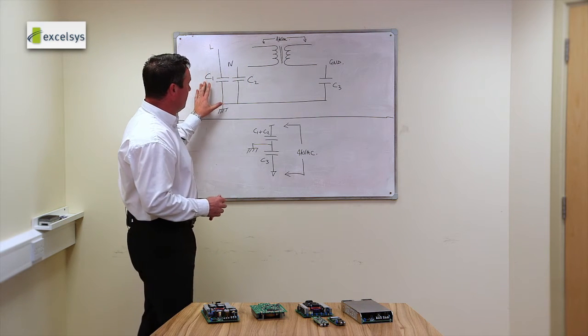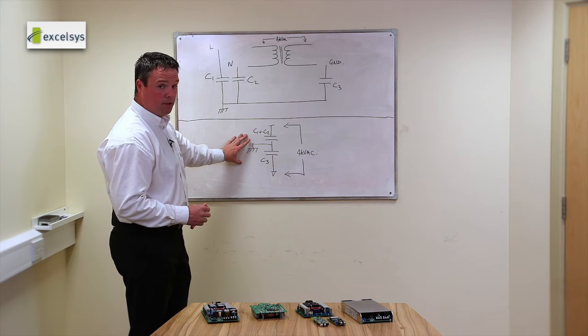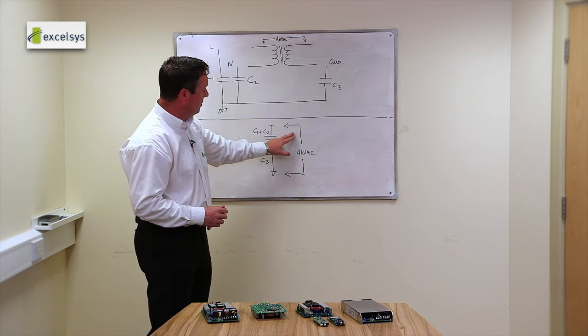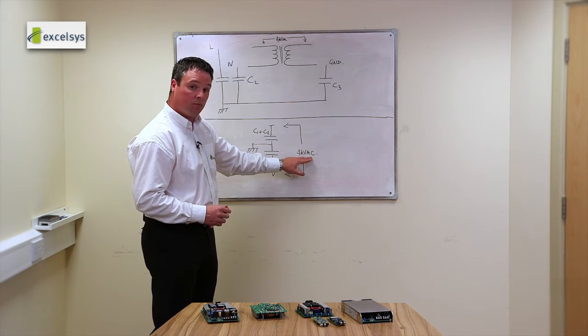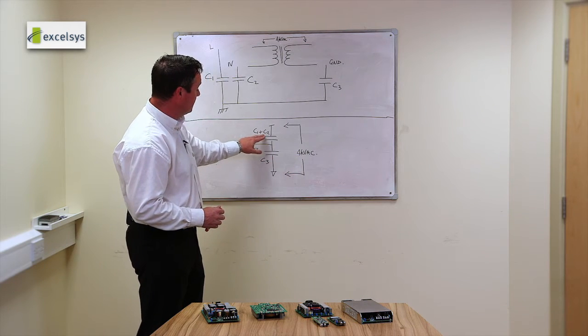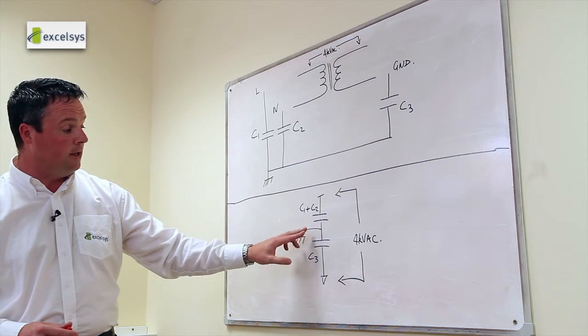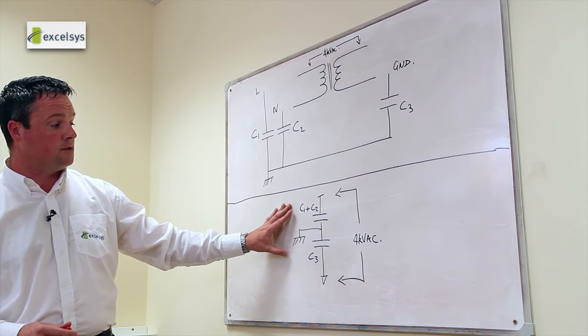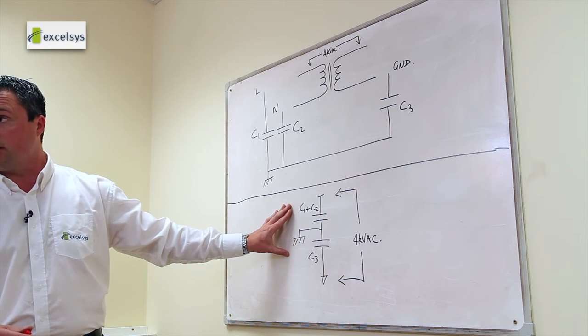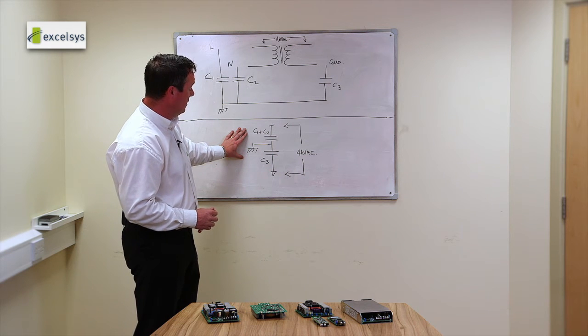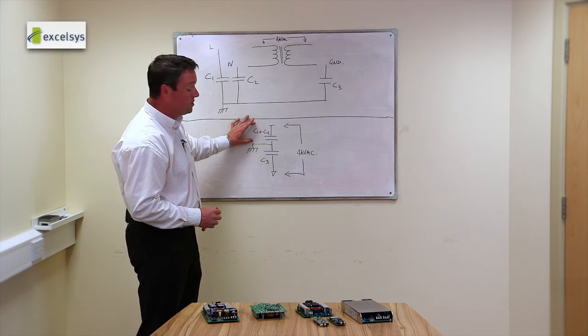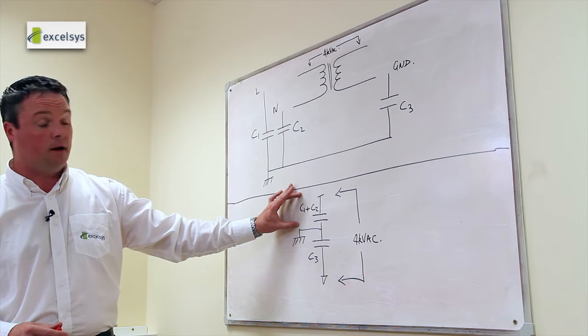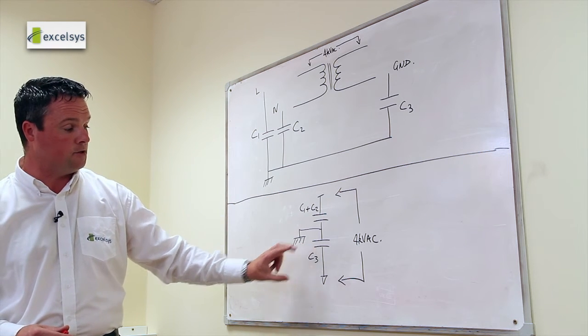So if we take this equivalent circuit and redraw it down here, you'll see that we apply 4kV AC across C1 and C2 in parallel and then in series with C3. Now very quickly you can start to see why damage may occur here. And the reasons for are the voltage divider effect on a combination of C1 and C2 and C3.